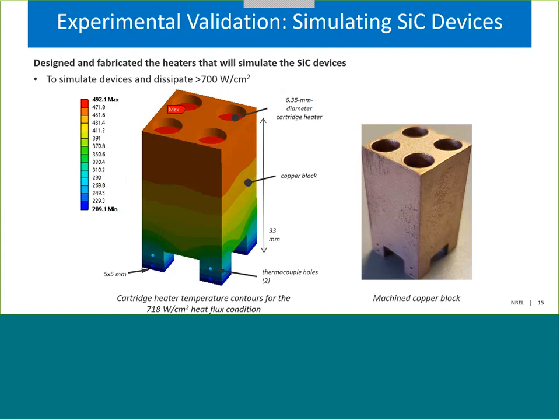And so we created this custom system that used cartridge heaters that were embedded within a copper block. The base of the copper block had these 4 legs, and each leg had a footprint of about 5 by 5 millimeters, which is equal to the footprint of the silicon carbide devices that we're simulating. Each of these legs represents a silicon carbide device. For the experiments, we're going to be using 3 of these copper blocks to represent the 12 devices. Within each leg, we are embedding 2 thermocouples to measure the temperatures and also to compute the heat fluxes through each of these legs.